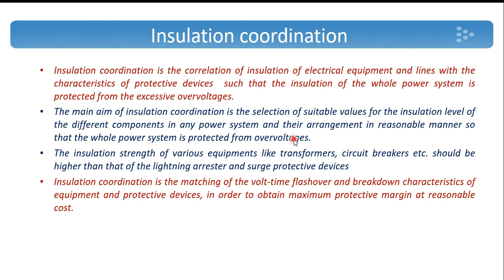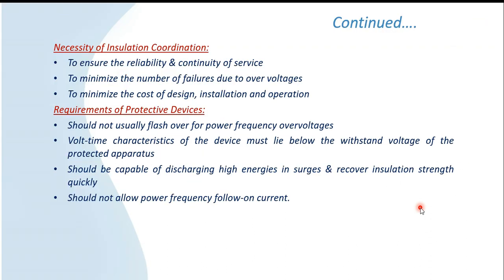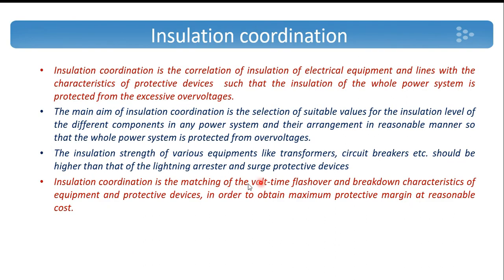The insulation strength of various equipments in power systems like transformers, circuit breakers, transmission lines, etc. should be higher than that of the insulation strength of protective devices like lightning arrestors or surge diverters. So insulation coordination is the matching of flashover and breakdown characteristics of the equipment and the protective devices in order to obtain maximum protective margin at reasonable cost. For doing insulation coordination, it is required to have a volt-time curve.